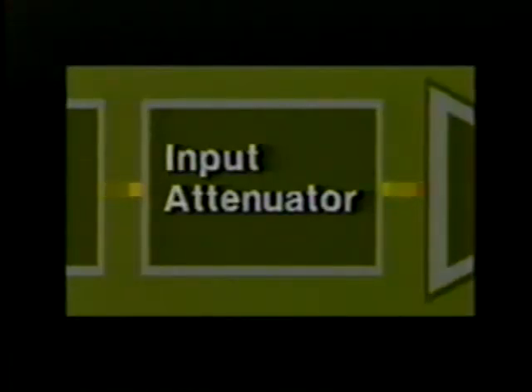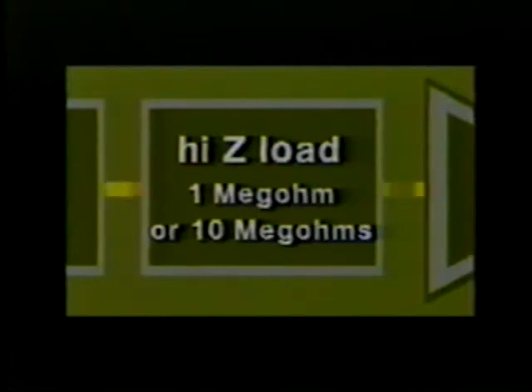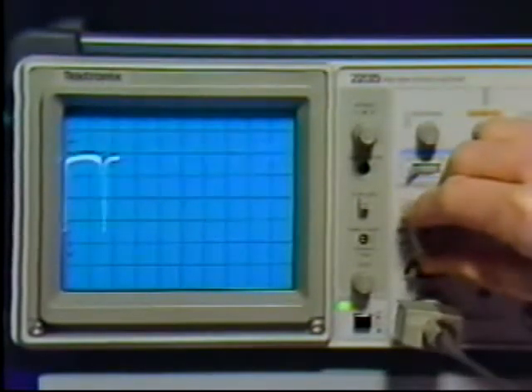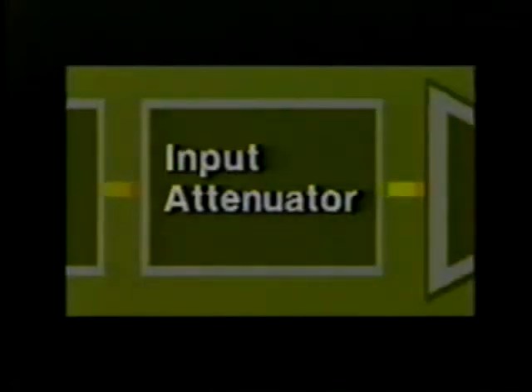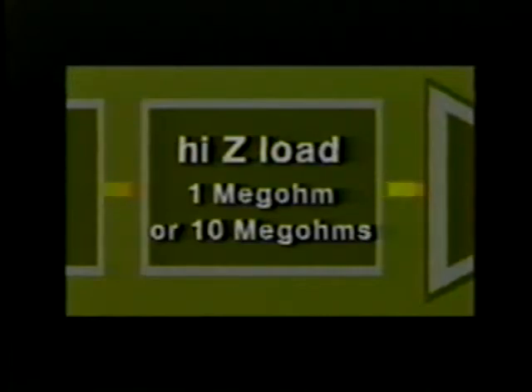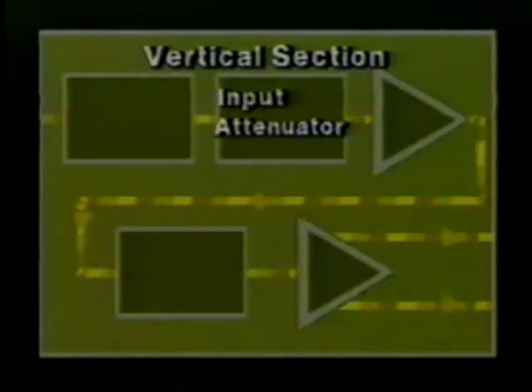The attenuator provides a constant high impedance load to the probe circuit, typically one megaohm or 10 megaohms with a times-10 probe. A constant load assures that any circuits after this point will not affect the source of the applied signal. The attenuator block also provides a means for reducing the signal to a desired level, creating a usable display on the CRT. In short, the attenuator block does two things: it provides a constant load for the applied signal, and it allows signal reduction.